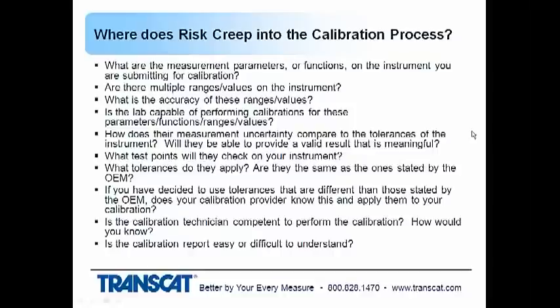And what test points will they check on your instrument? We've seen examples where a calibration for, let's say, a temperature indicating device that had 2 channels and 4 different thermocouple types on each channel was only checked on 1 channel and 2 thermocouple types, yet the instrument in the production process was used on both channels and 3 out of the 4 thermocouples. There's no traceability for the channel that wasn't checked or for the other thermocouple types that were not checked, and therefore they have no control over their measurement process. They have no indication whether that meets or does not meet the tolerances of the instrument, and that's the basis of their use of the instrument in their process. So it's not capable of producing valid results if it's not being checked.